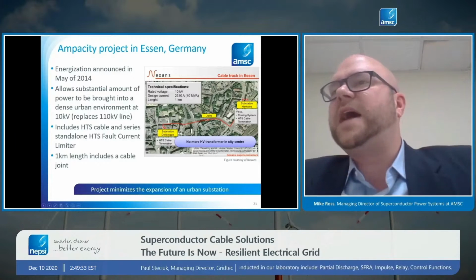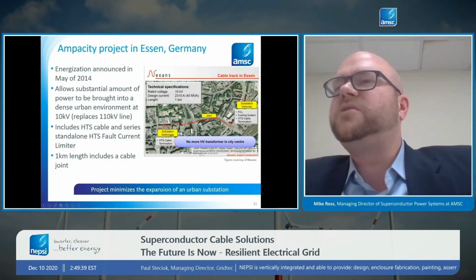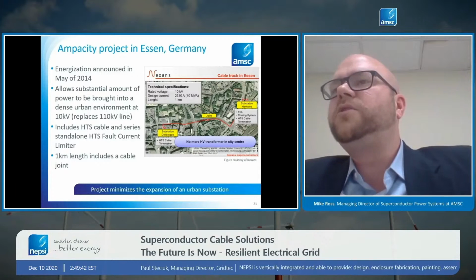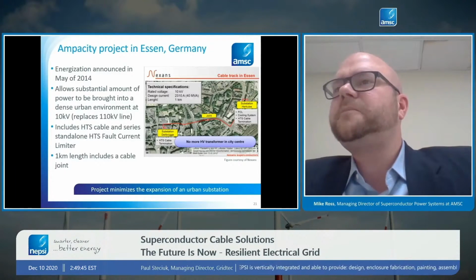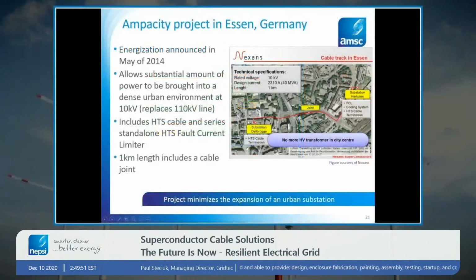The application is that you had a downtown substation called Dellbrügge. This is a European city that has the typical pedestrian core, so all of the utilities are underground. And then they had a problem where the city was growing and they needed to add more power to this substation. And the way they would normally do that is they would bring a 110 kV transmission cable from the suburbs into the new station and then install a 110 to 10 kV transformer, and then you would increase the power capacity of the substation in that way. But there was no room. It's an underground substation. There's no place to put a great big 110 to 10 kV transformer.